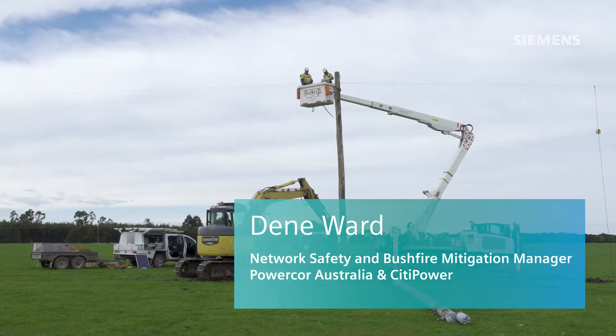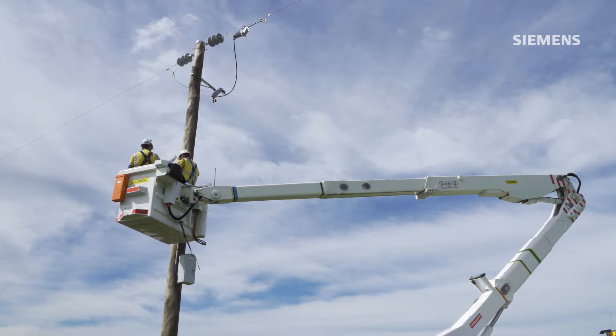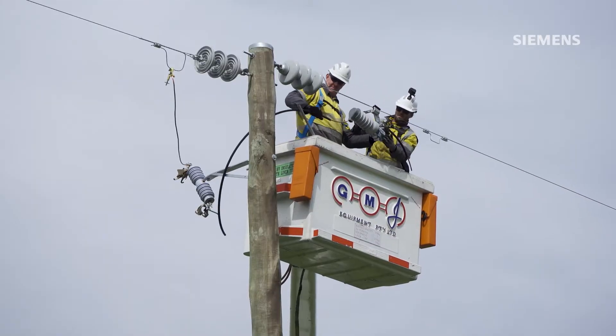Powercor has over a thousand single-wire earth return systems on our network, and as part of the revised bushfire mitigation regulations, we're required to put a high-speed protection device at the front end of all of those systems. The attraction of the fuse saver was its compact size and the fact that it had a very high-speed interrupting cycle, which was attractive from a fire safety risk reduction perspective. Siemens were also willing to work with us on implementing a re-close capability.